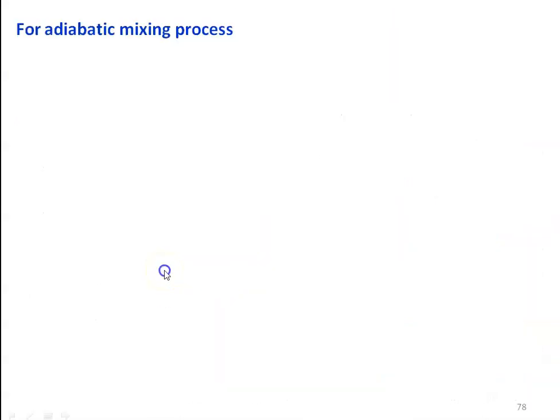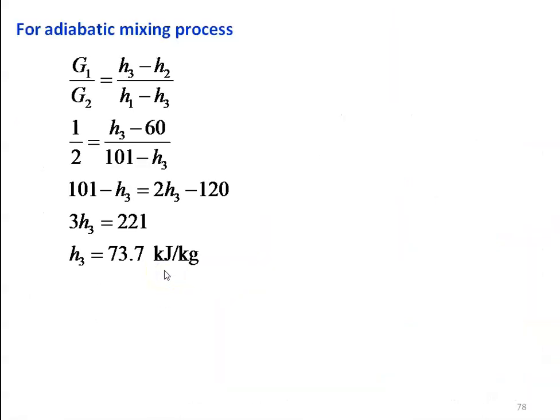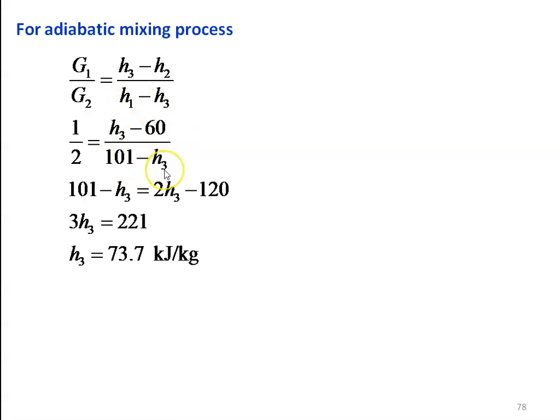For the adiabatic mixing process, we have the ratio G1/G2 = (H3 − H2) / (H1 − H3). G1 = 1 kg, G2 = 2 kg, H3 is the unknown. Substituting: 1/2 = (H3 − 60) / (101 − H3). Solving this equation, H3 = 73.7 kJ/kg.